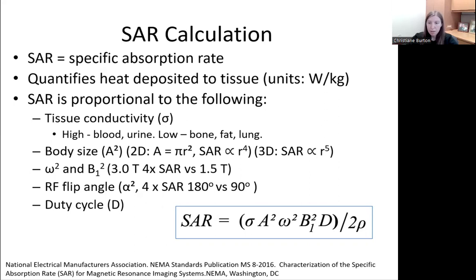Foreign metal objects in the body are frequently highly conductive and significant. Even dangerous heating levels around these may occur. SAR increases significantly with body size. In a 2D model, SAR is proportional to the square of the body cross-sectional area. Because A is equal to pi r squared, where r is the radius of our patient, our model predicts that SAR is proportional to the body radius to the power of 4. When the third dimension is considered, SAR actually proves to be more closely proportional to r to the power of 5. SAR tends to be more concentrated around the periphery where the radius is larger.